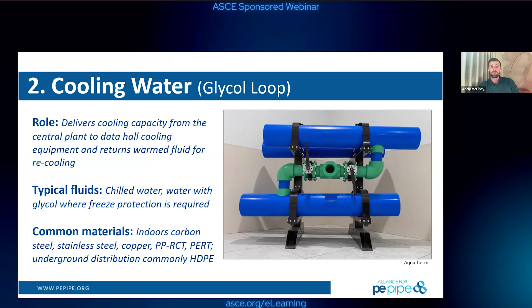And then the heat exchange loop—this is related to our last one—these are your primary fluid networks, running chilled water to your fan walls to essentially remove the heat from your hot contained aisles. They historically have been carbon steel. As we go direct-to-chip, your options become really stainless steel or a fusible solution.